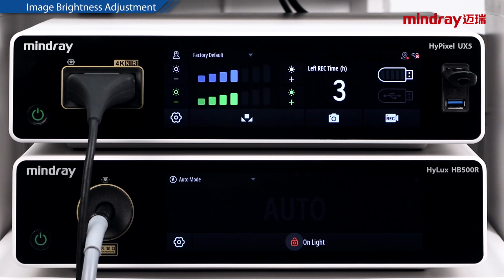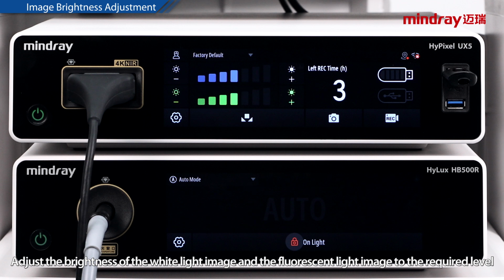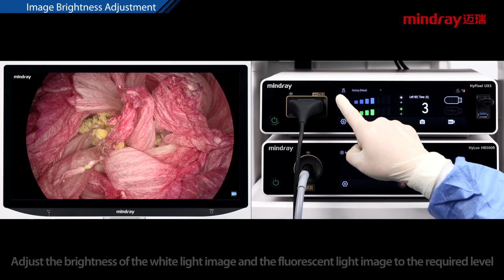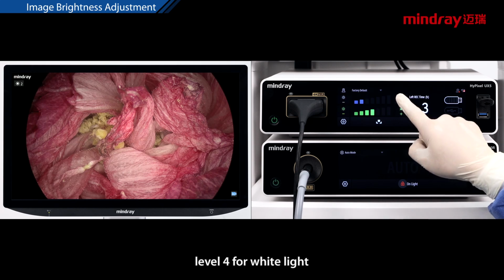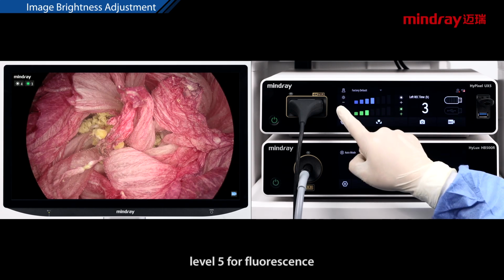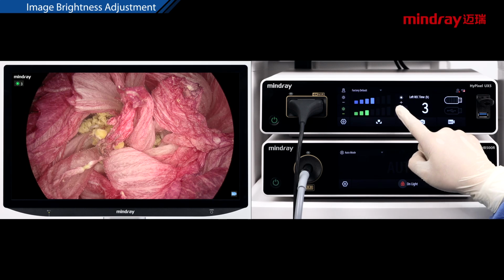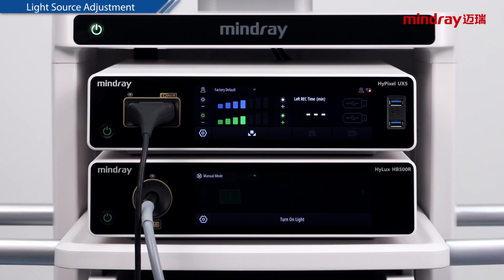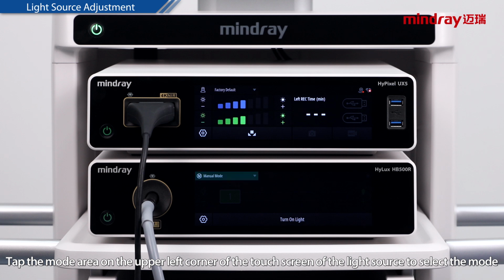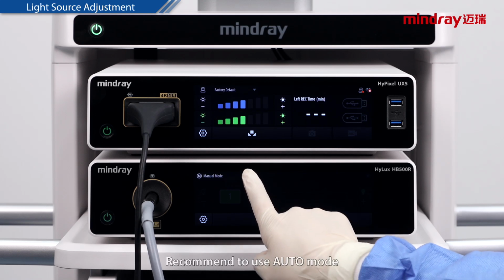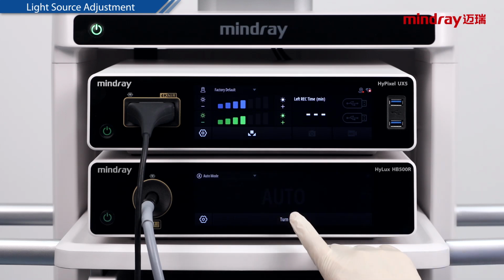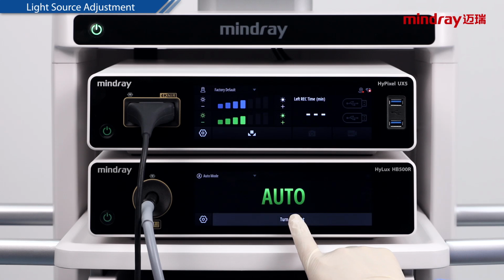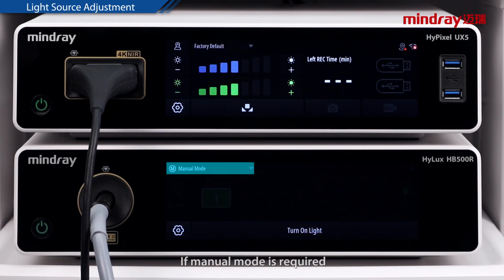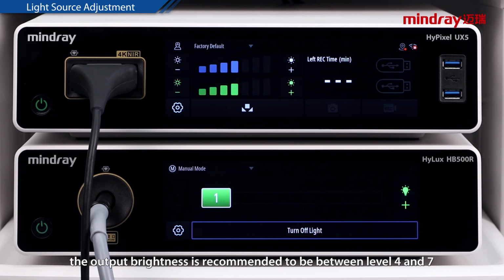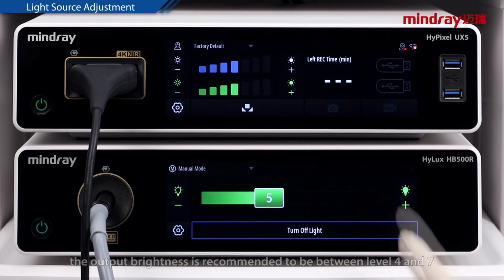Image brightness adjustment. Adjust the brightness of the white light image and the fluorescent light image to the required level. The recommended brightness is Level 4 for white light, Level 5 for fluorescence. Light source adjustment. Tap the mode area of the upper left corner of the touchscreen of the light source to select the mode. Recommend to use auto mode. If manual mode is required, the output brightness is recommended to be between level 4 and 7.